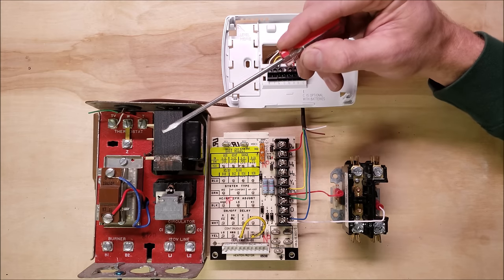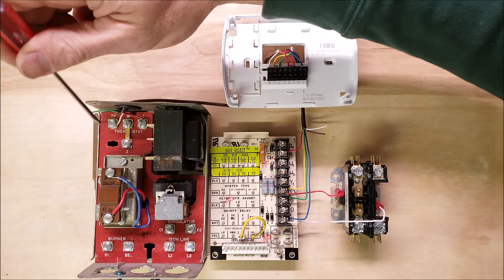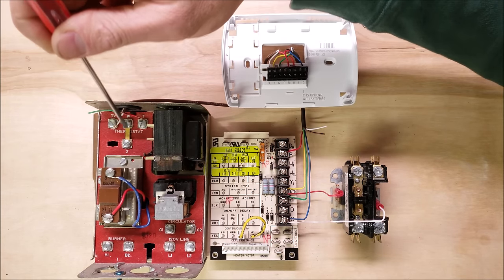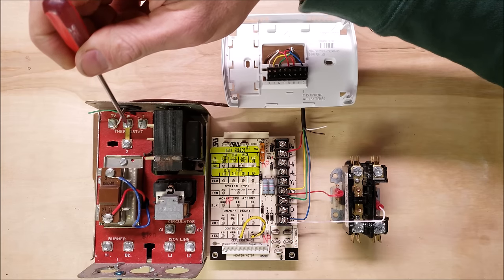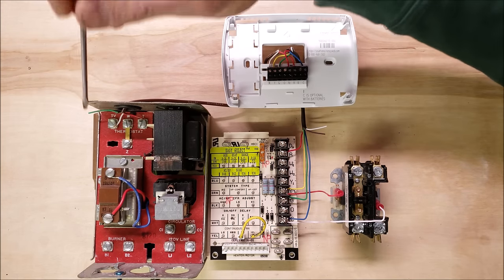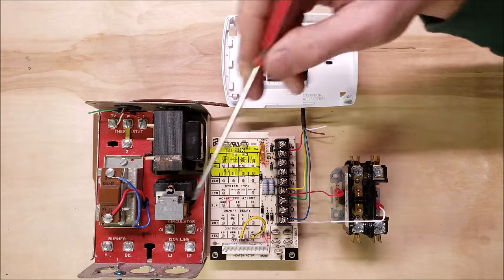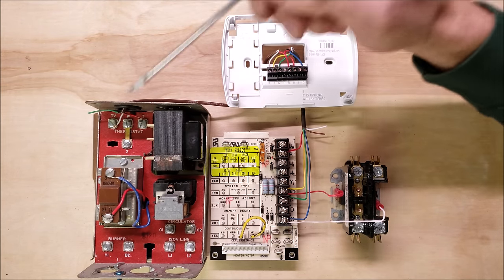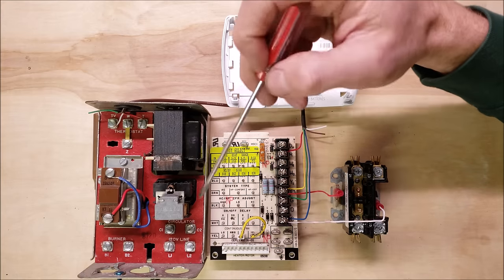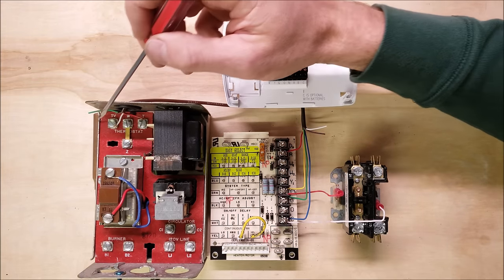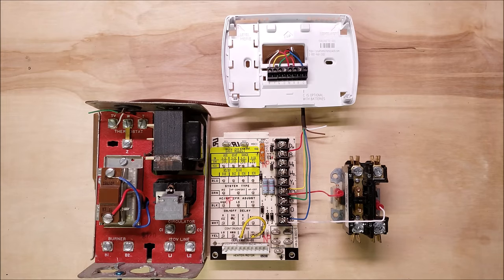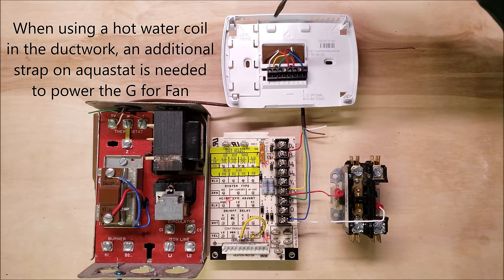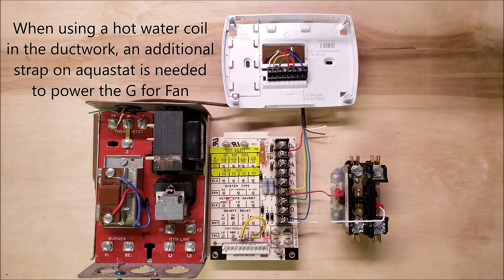Here's an Aquastat out of a boiler with TV and T wired onto it. On this particular Aquastat controller you have T as the 24 volts heading out, and TV is a signal for the circulating pump to circulate hot water. You could have a different Aquastat so it may be T and T terminals or R and W terminals, and then here you have your thermostat sub base.